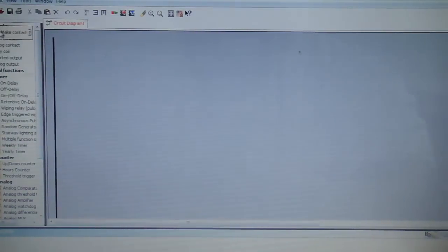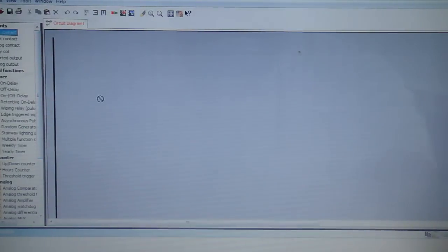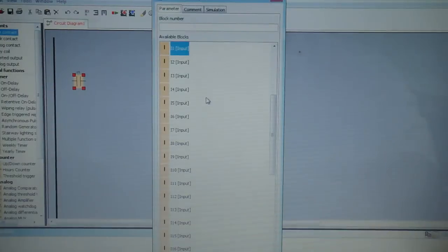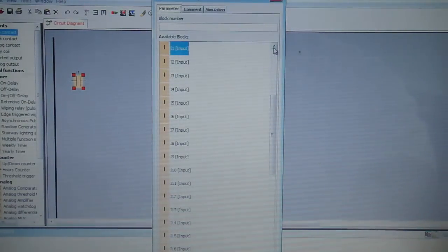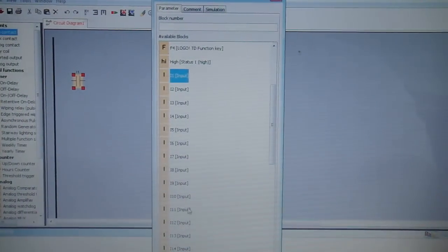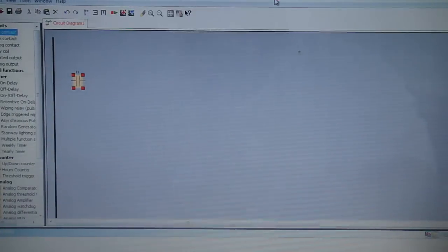Let us first create a simple program and see how it works. From this menu you can select contacts, or break contacts which are normally closed, analog contacts, and relay output, inverted output — whatever functions you need, including timers and delay timers. When you place a contact it asks you which input you need: I1, I2, I3 — we have eight inputs as mentioned. You can select one and change it later.